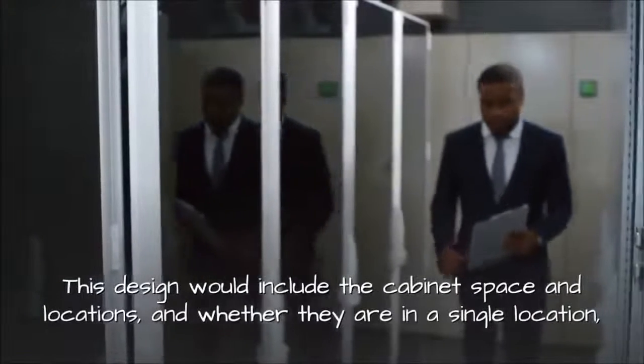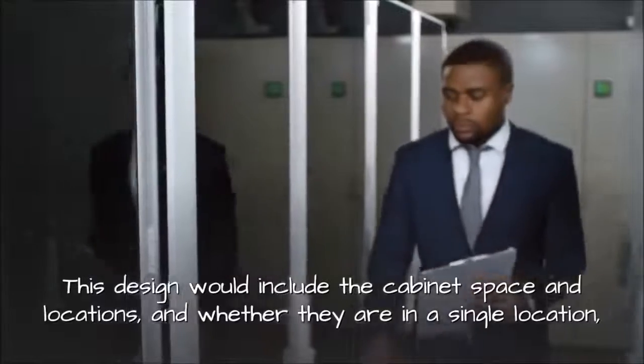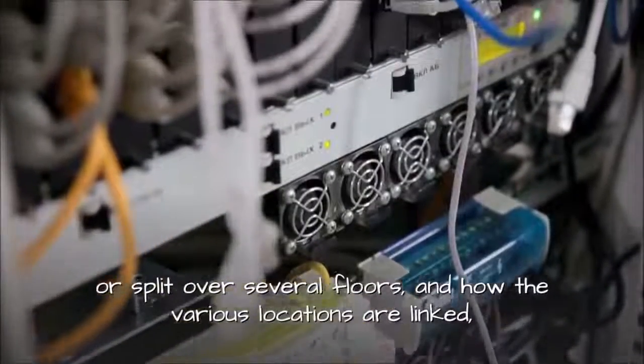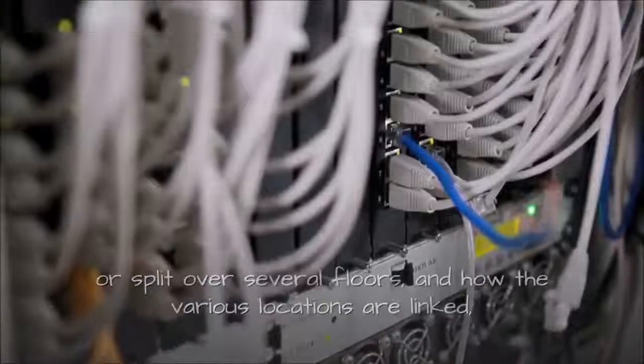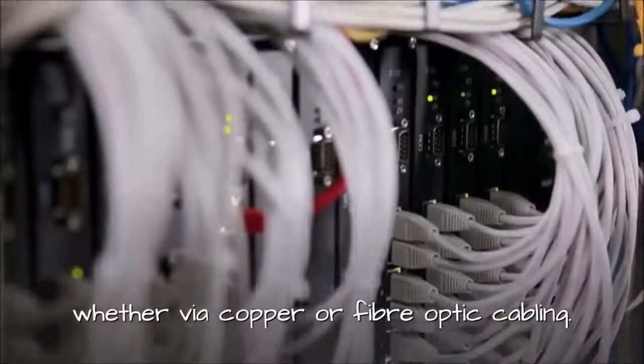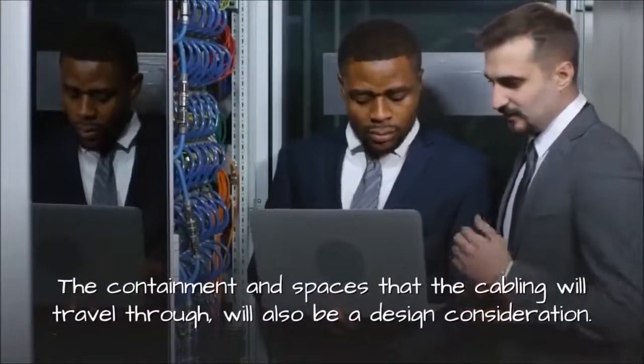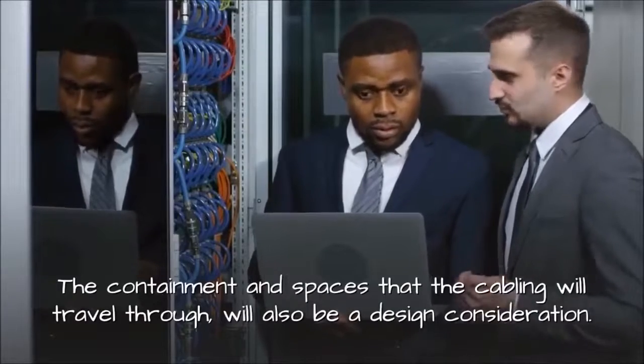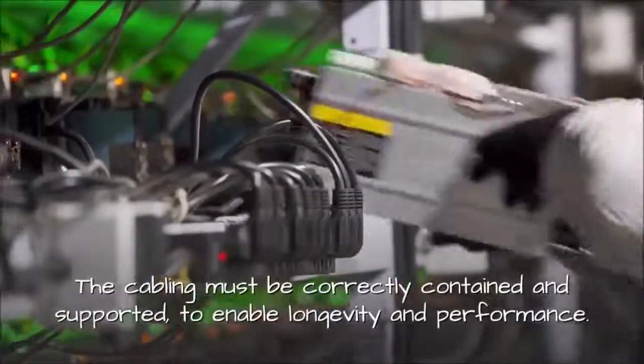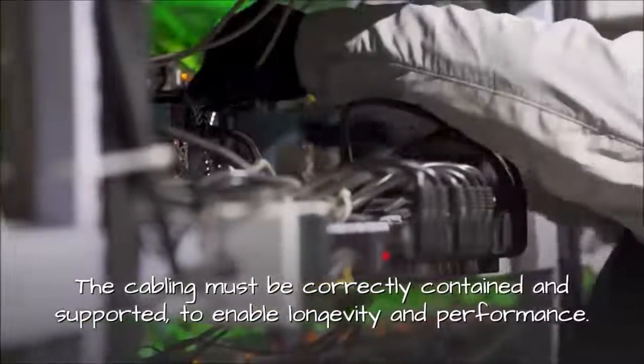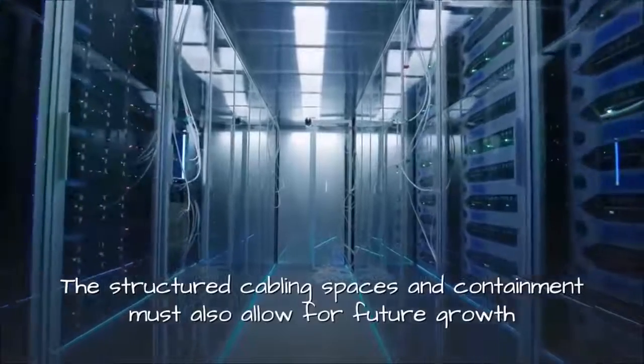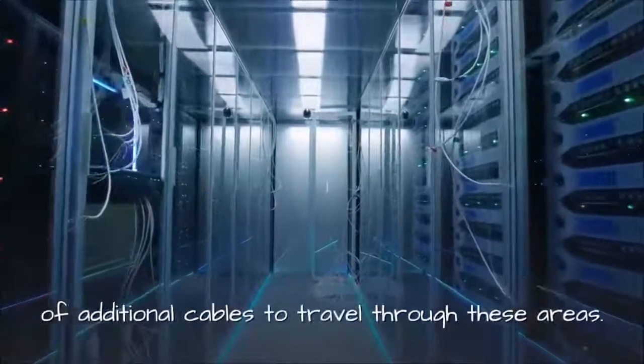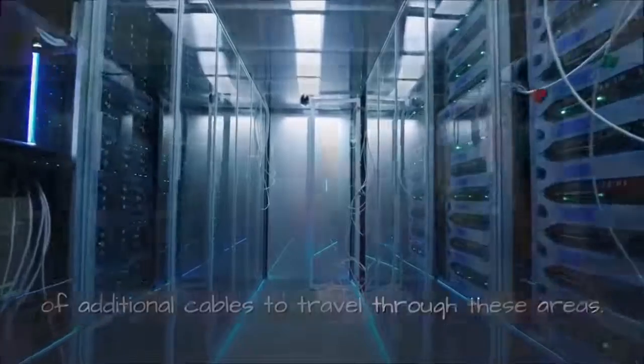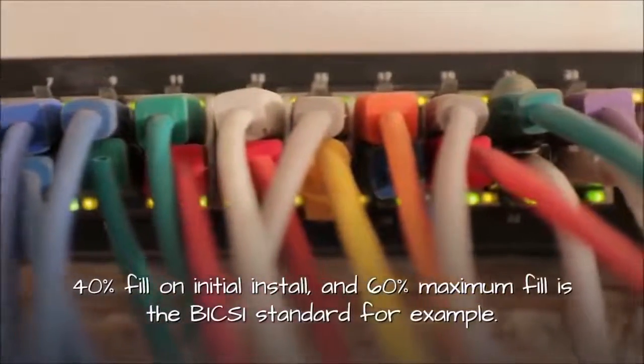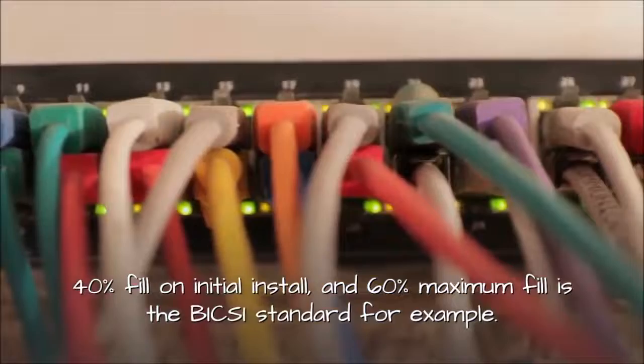This design would include the cabinet space and locations, and whether they are in a single location or split over several floors, and how the various locations are linked, whether via copper or fiber optic cabling. The containment and spaces that the cabling will travel through will also be a design consideration. The cabling must be correctly contained and supported to enable longevity and performance. The structured cabling spaces and containment must also allow for future growth of additional cables to travel through these areas. 40% fill on initial install, and 60% maximum fill is the BICSI standard.